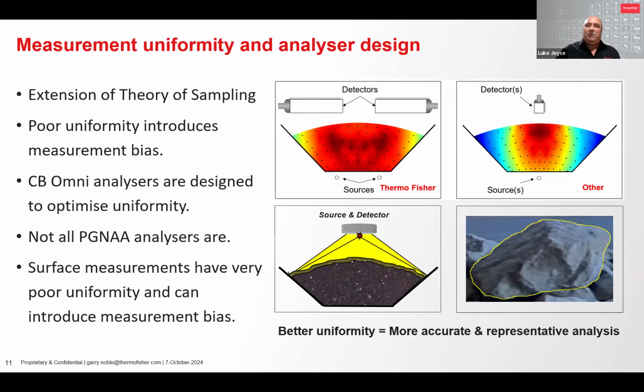Thermo Scientific PGNAA analyzers are designed to optimize uniformity of measurement, as shown in the top left image. However, other PGNAA analyzer designs do not deliver measurement uniformity. The example in the top right shows an analyzer design with a centered source and detector configuration. Some designs have the neutron source on top and detector below. Both provide poor lateral and vertical uniformity, which can therefore introduce measurement bias. Other measurement techniques used online on belts and on shovels only provide surface measurements, so would only measure the surface layer of the material or the surface of falling rocks. In either case, every element below that penetration depth will certainly not be included in the analysis and would almost certainly introduce measurement bias.